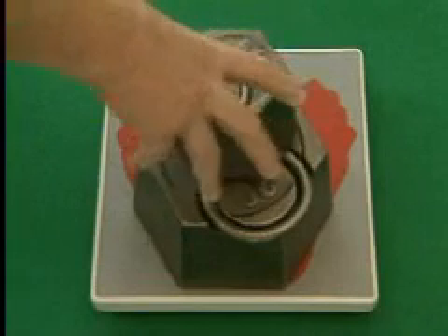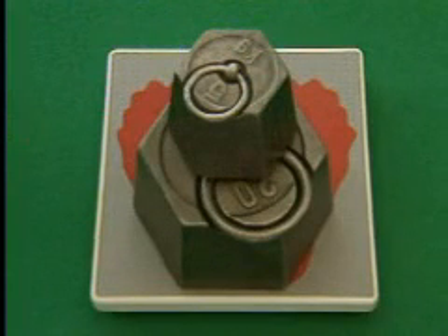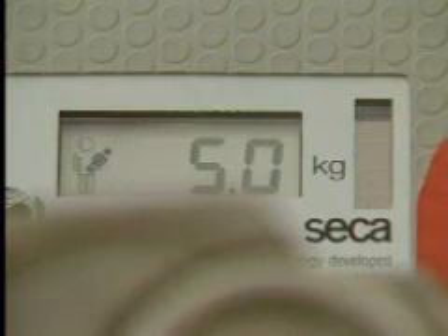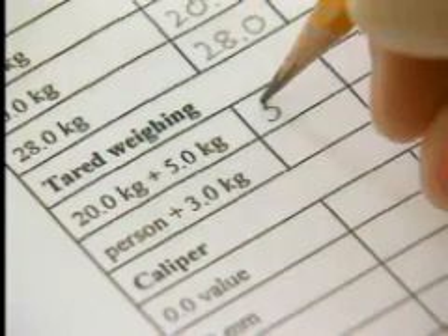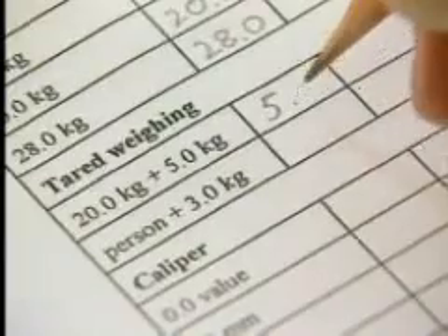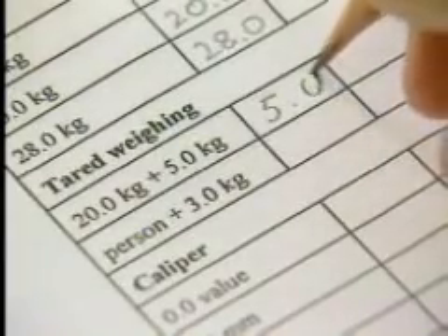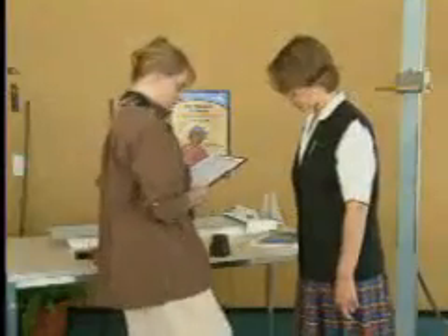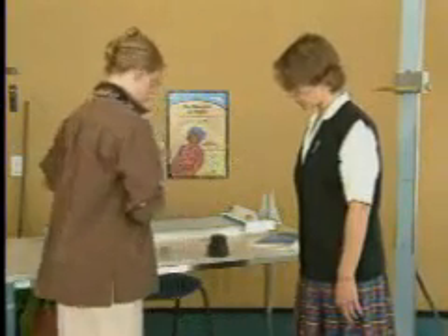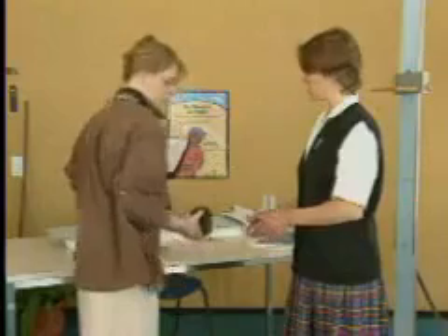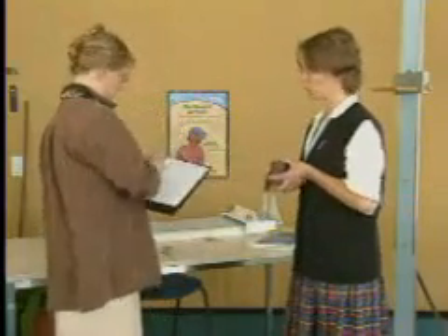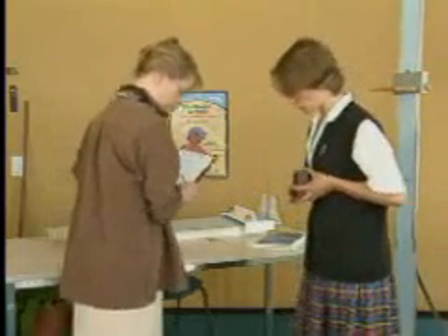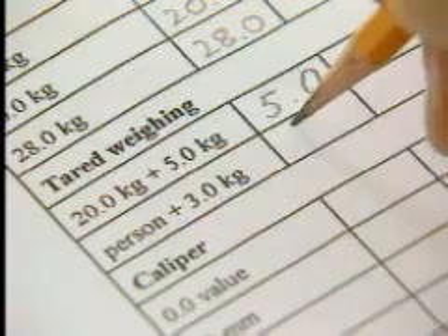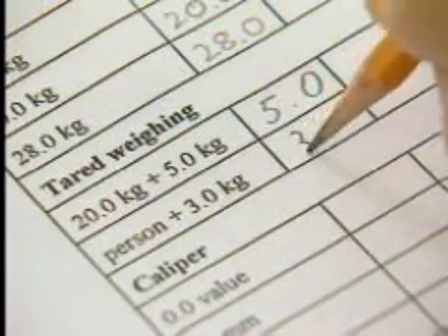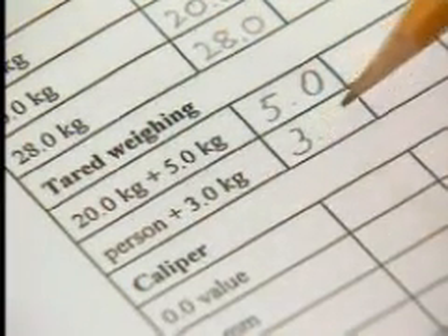Tare the scale with the 20 kilogram test weight and weigh the 5 kilogram test weight. Record the result on the calibration form. Tare the scale again with an adult standing on it and weigh the 3 kilogram test weight. Again, record the result on the calibration form.